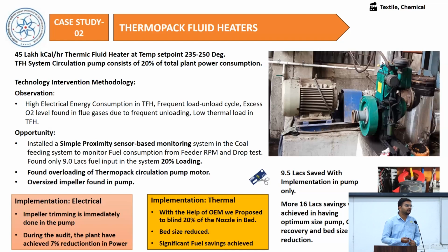We measured the power consumption, we measured everything, and we observed frequent loading and unloading in the thermic fluid pumps. The reason for the loading unloading is the capacity of the thermic fluid heater system. There is a 45 lakh kilocalorie thermic fluid heater system which is running on only a 9 lakh kilocalorie load, so it is running at almost 20% loading. Whenever the thermic fluid system achieves the temperature, it will cut off the bed, and after that it will start again after the temperature reduces. In this pattern, they are having frequent start-stop cycles.